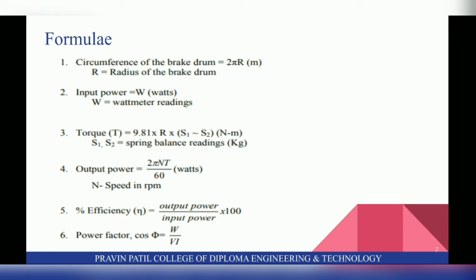So these are the formulas, in which first is circumference of the brake drum is equal to 2 pi r, in which r is radius of the brake drum. Second is input power, that is W watts, where W is wattmeter readings. Third is torque is equal to 9.81 into R into S1 minus S2, where S1 and S2 are spring balance readings. Fourth is output power is equal to 2 pi NT upon 60 watts, where N is speed in RPM.